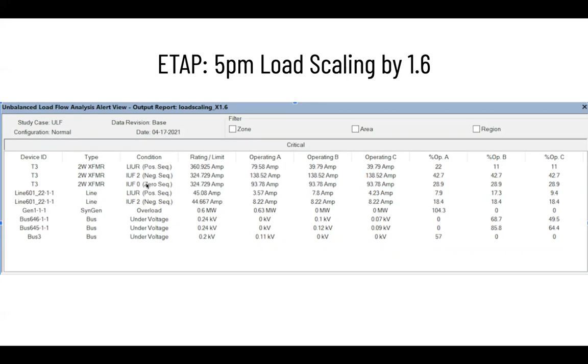And once again, we can see the under voltages on the residential area. So in this case, this is one of the cases that we used for 12 p.m. from our data, which we used to relocate our PV system generation to bus 632, due to the fact that previously it was not sustaining our system. But in this case, it's determined that it slightly sustains our residential area, which is reaching some nominal value of 99.